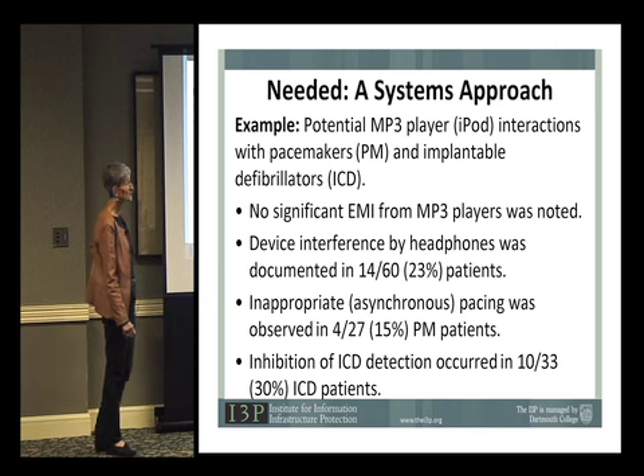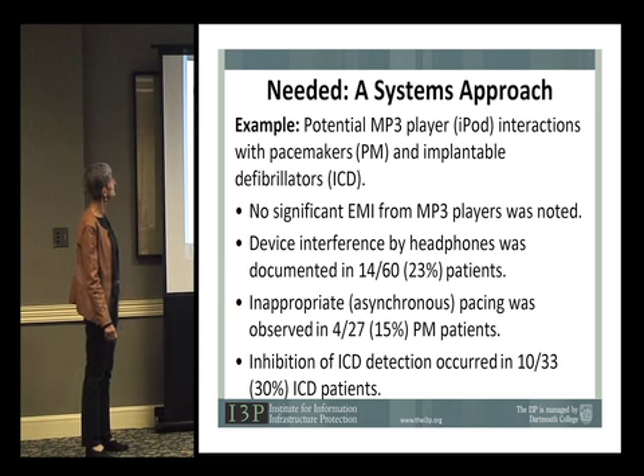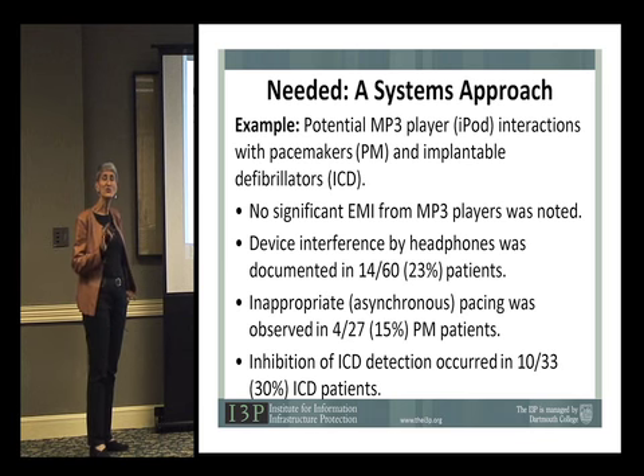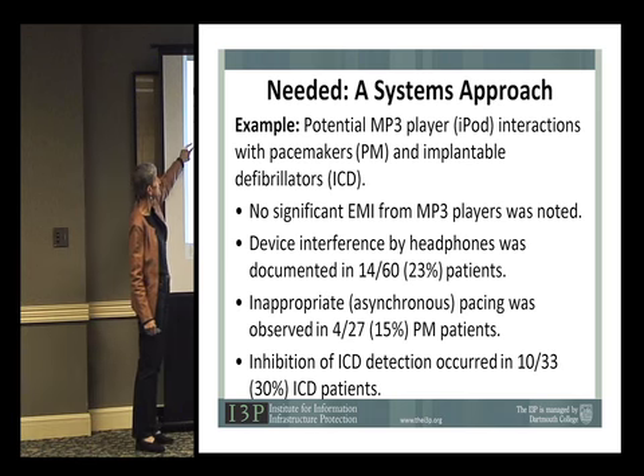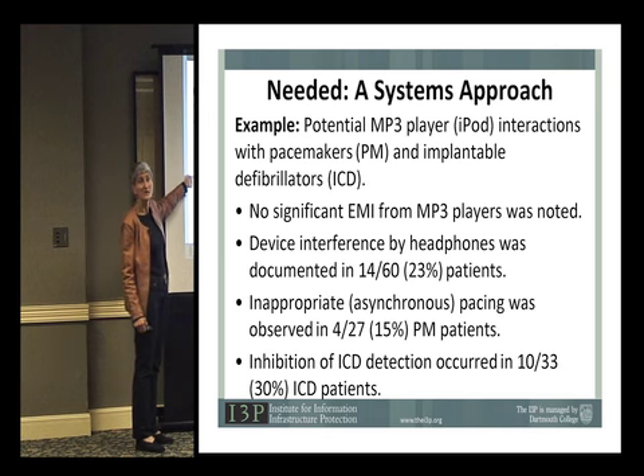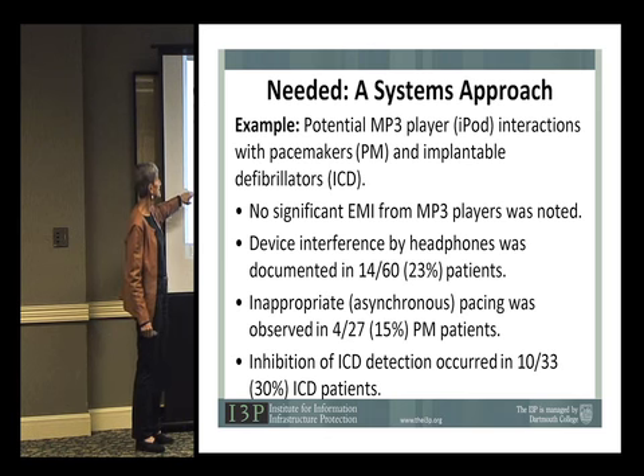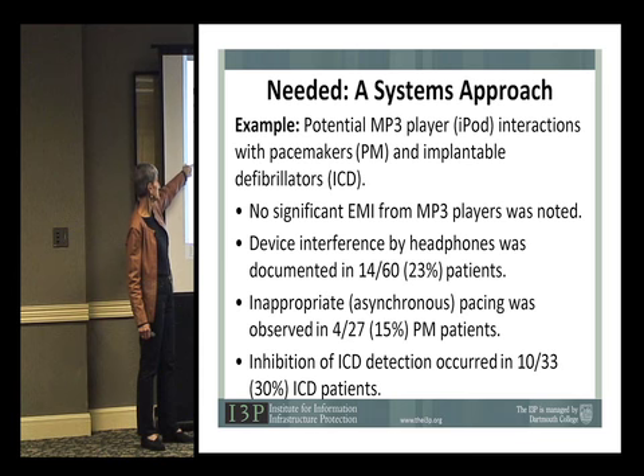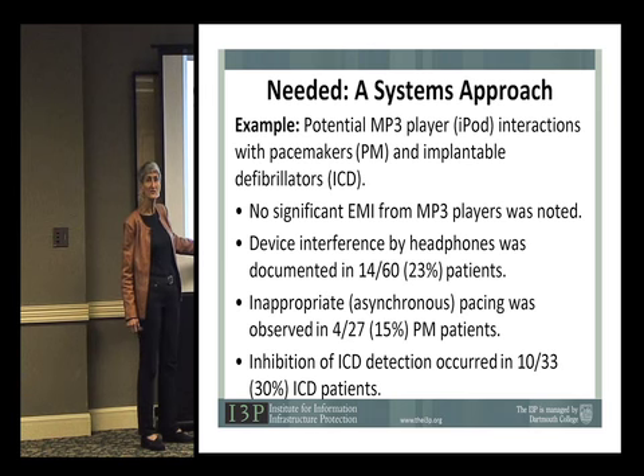So here's an example also coming from Kevin Fu's research group. They wanted to look at MP3 players. They used iPods interacting with pacemakers and implantable defibrillators. And their initial goal was to see whether, if you're listening to something on your iPod, that interferes with your pacemaker or your defibrillator. And they found that actually no, there wasn't any problem between the iPod and the defibrillator. But what they did find was that there was interference from the headphones. That in 14 of the 60 patients, there was demonstrated interference, and it actually affected the pacing in the pacemakers in 4 out of 27 pacemaker patients. And it inhibited the defibrillator detection in 30% of the devices. So they started out looking at one thing, but they found another thing that was a real problem.